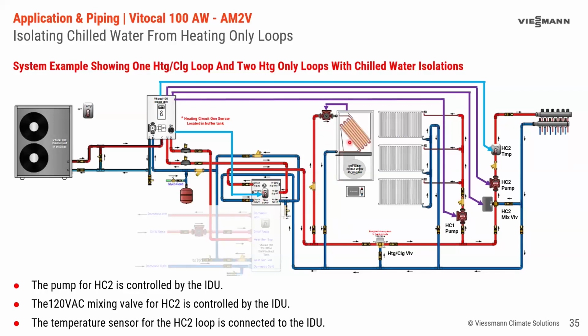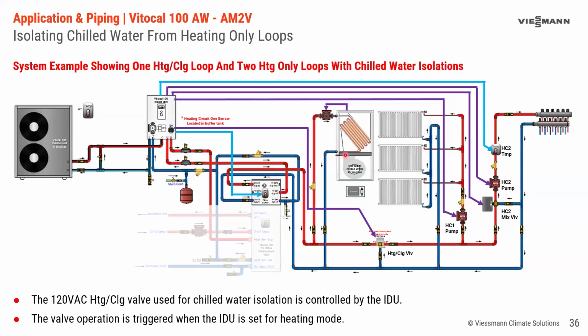So you don't have this thermostat or the call for heat from the air handler coming back here. You don't have an end switch on a zone valve coming back here. You just have these running as a building loop and pulling energy off the buffer tank, and the buffer tank's being maintained. Now, when I've done it this way, you can see that it might be even more important to have this bypass valve in here, because we have 2 circuits. One's hot water, chilled water, and one's hot water on the same energy circuit. So again, this valve here becomes more important because we certainly do not want chilled water running to these radiators.